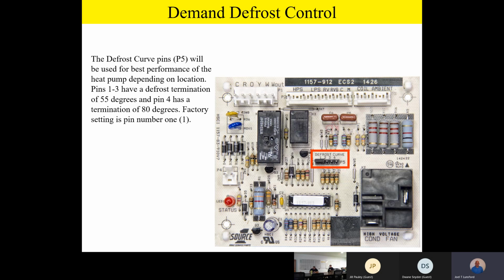And what they do is, when they're in the test facility, when we're testing the equipment, there's going to be an optimal curve. There's going to be an optimal place. To give an example, let's say a 3-ton unit. I'm just making this up, but let's say at 20 degrees outside, the optimal coil temperature might be 15 degrees before it goes into defrost on that coil and that chassis, that combination.